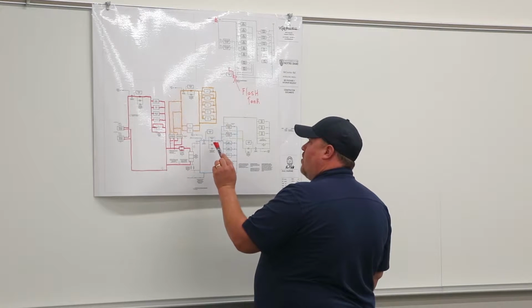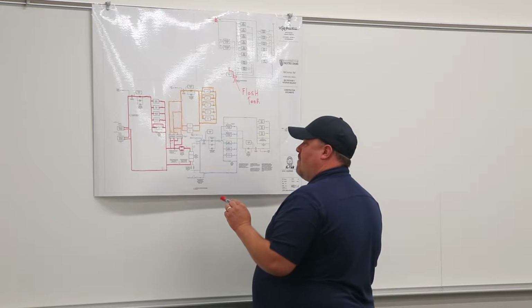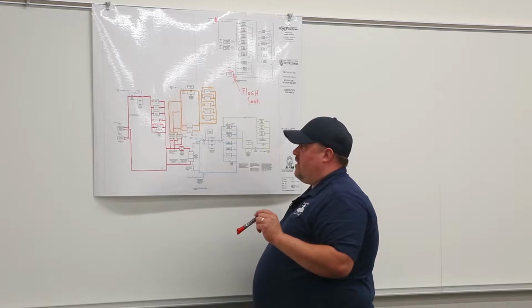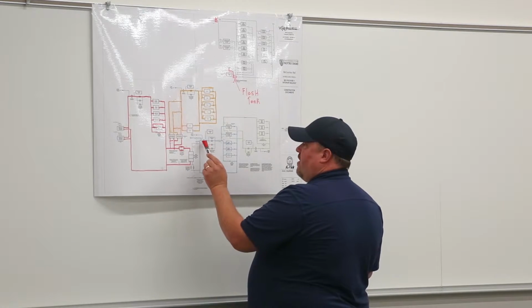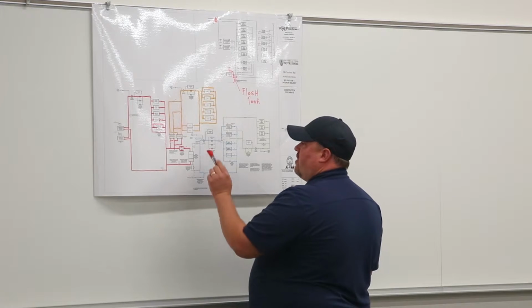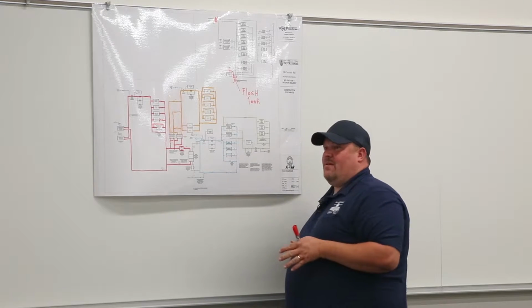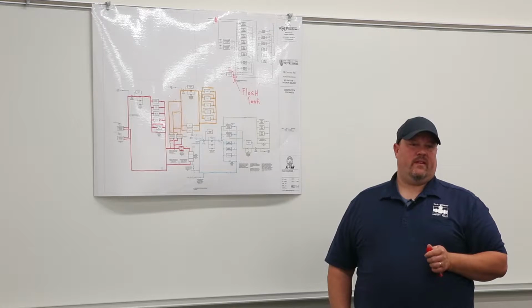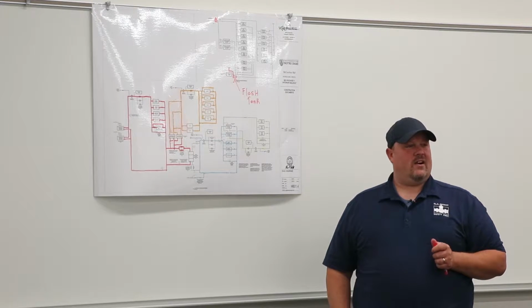We've got 3 12-inch pumps that are mounted along the east wall of the mechanic room. We've got these air and dirt separators that are installed as well. They take a little bit of maintenance. They need to be blown down like maybe twice a year, I do believe it is.